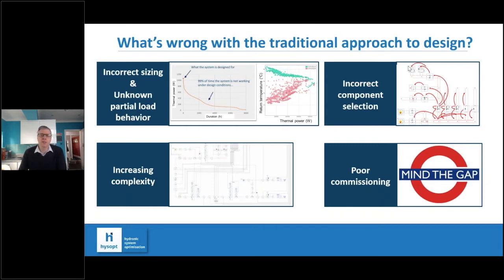Second issue is we're getting increasing complexity now. In the past, HVAC systems or even heat networks were fossil fuel boilers and pumps, and that was really it. Now we're seeing heat pumps, CHPs, thermal storage, heat from waste, all sorts of combinations of different heat sources, all of which perform differently under different conditions and different temperature regimes. So how do you best integrate all those things together to get them to work properly? And with increasing complexity comes increasing sensitivity to correct hydraulic design. So you need to get that right and understand how it's going to perform at the design stage.